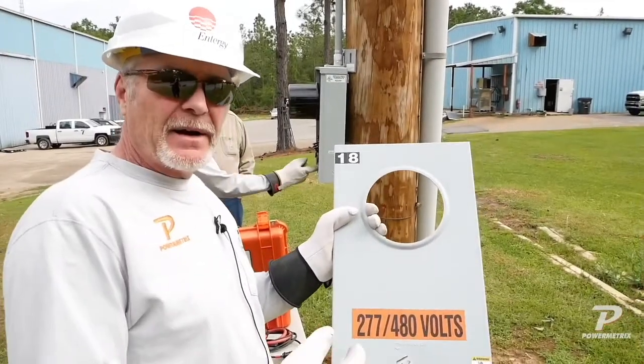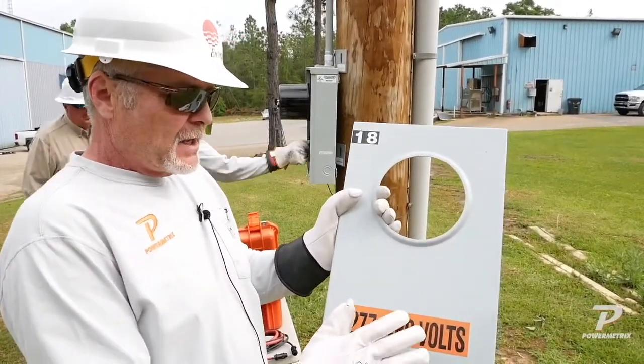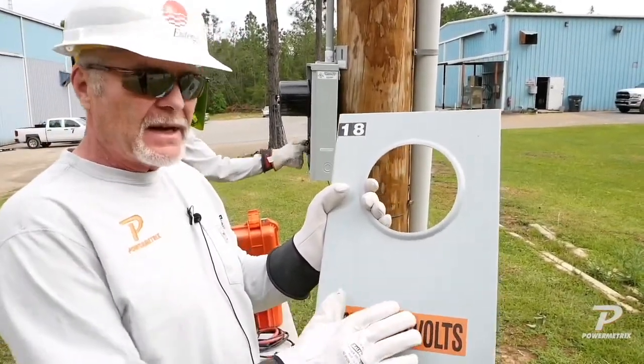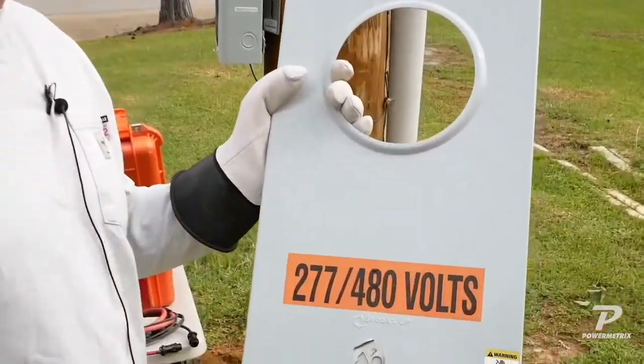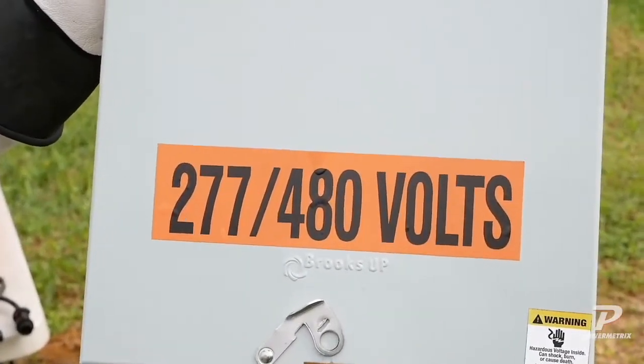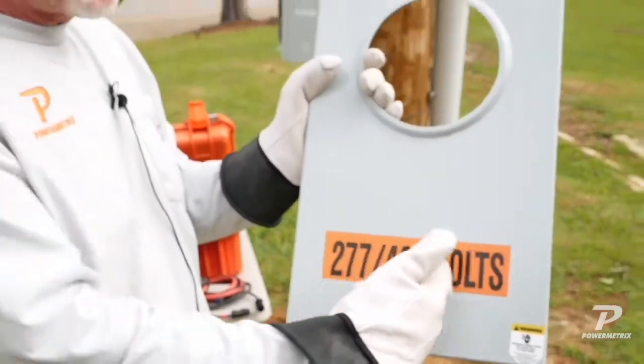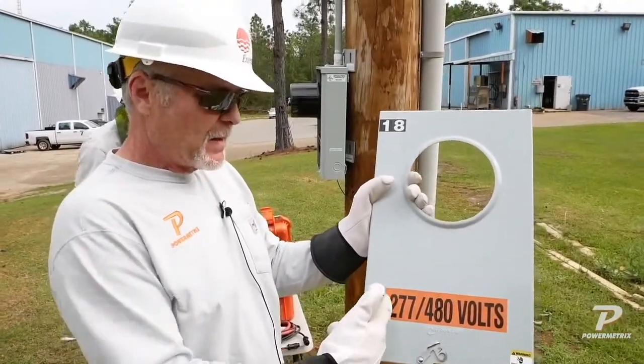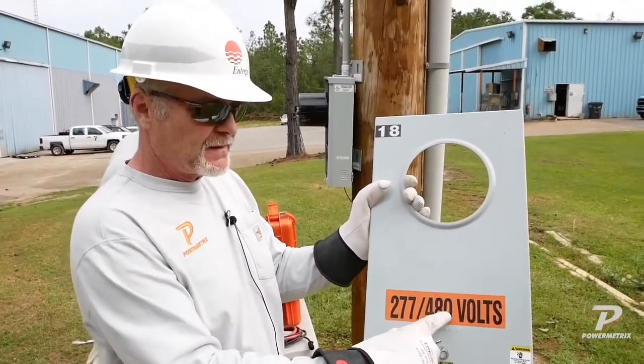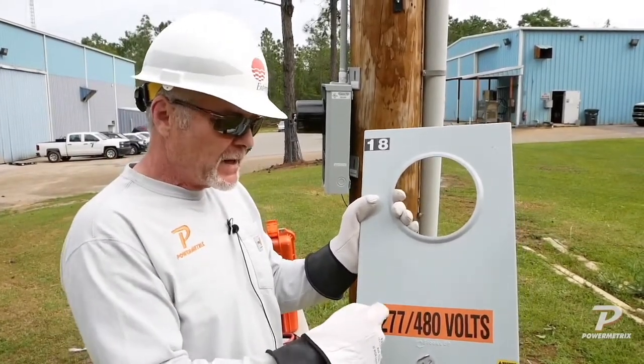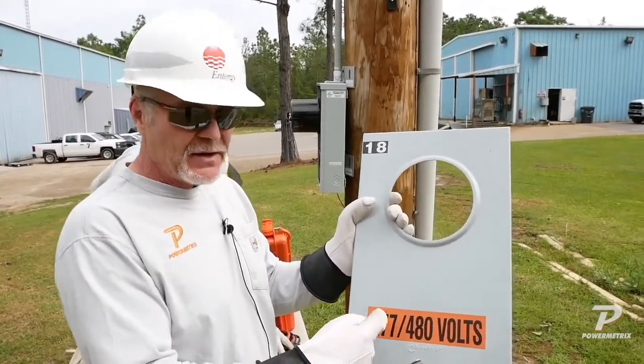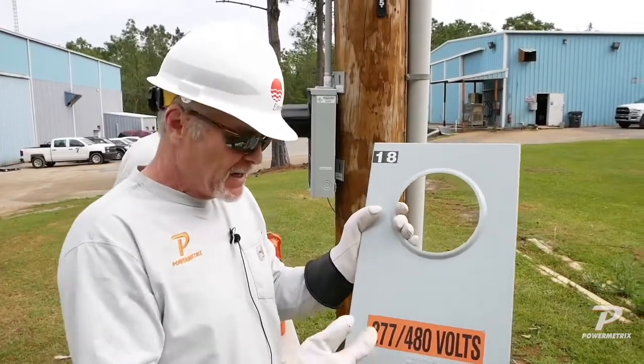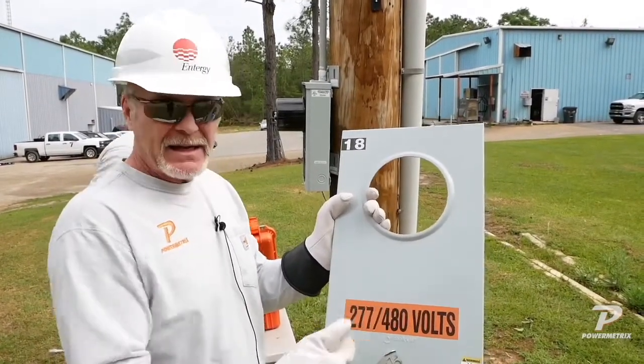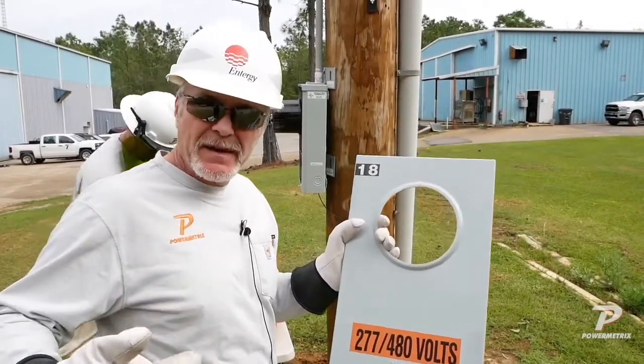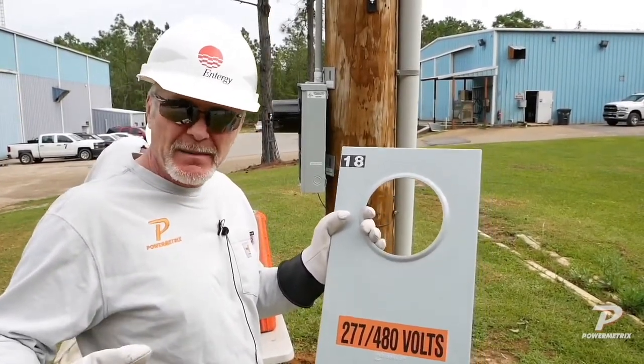While we're out here, we may as well point something out. With the utility company, there's a lot of differentiation on what safety equipment you have to wear, depending on what you're dealing with at the site and the voltages involved. They've put a label here showing 277, 480 volt, so if someone walked up they'd know it's not a straight 480 site. This number might let someone know what safety equipment, what level of PPE, they need to be wearing.